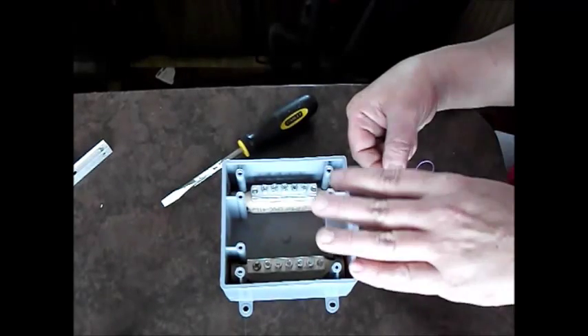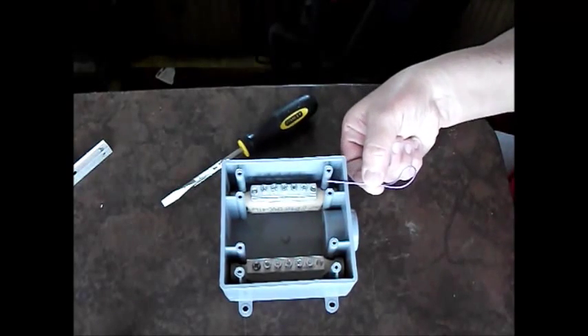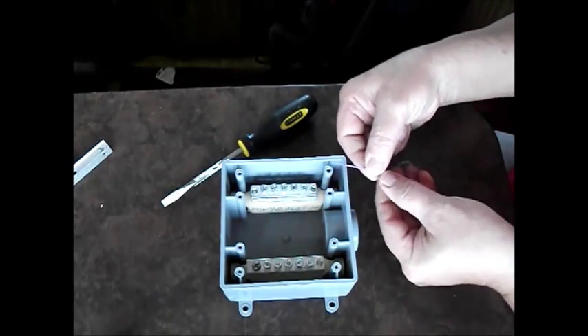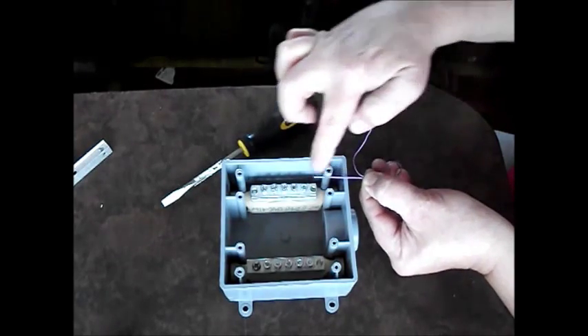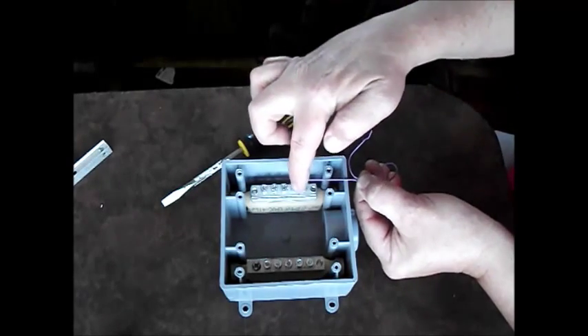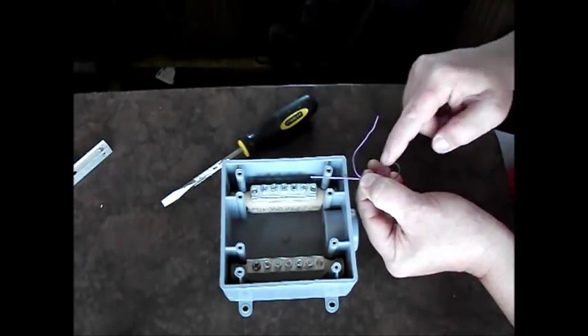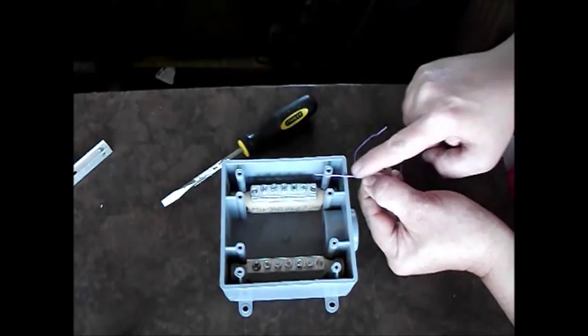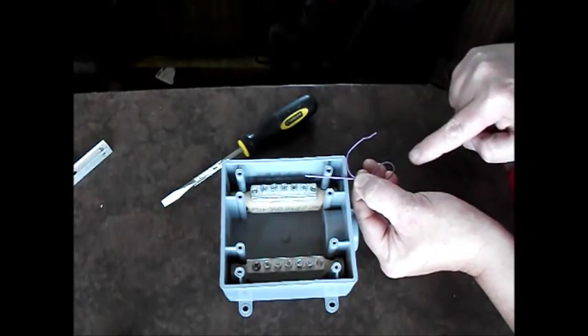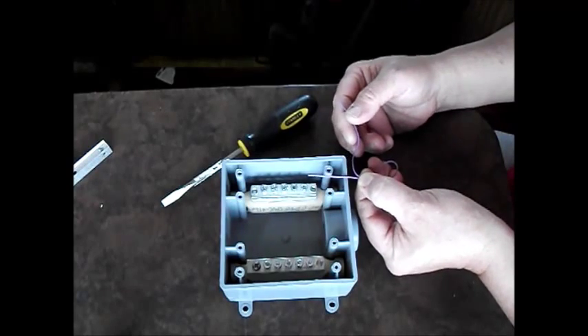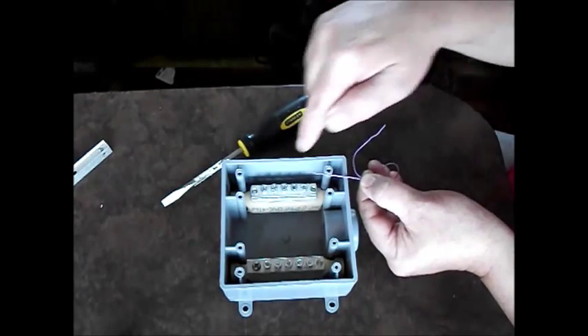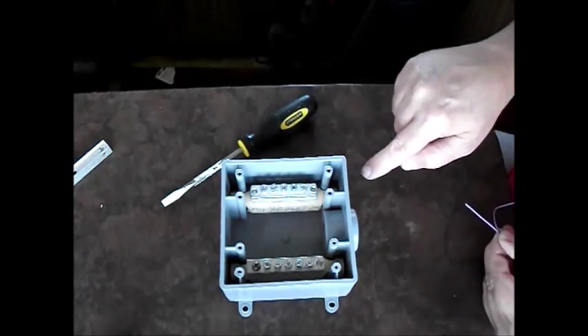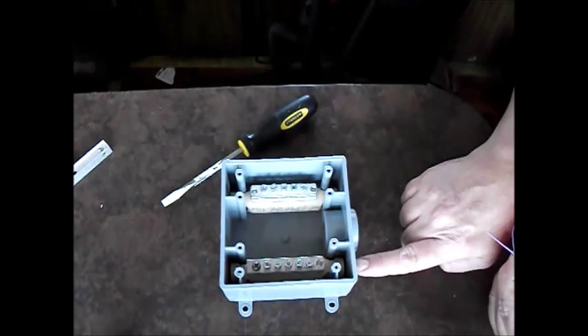But it'll drop down like this, and then whenever rain comes along, this wire goes off to the solar panels, this wire goes in here and makes our connection here, this end of the wire will make our connection here, and this will go to the solar panels. The rain will come down this wire and it will come down here and it won't be able to go back up. It will actually drip off the end of this little drip loop. So that's how we'll take care of any problems as far as water getting into the box, because you'll have a drip loop. You'll have four drip loops on this side and four on this side.